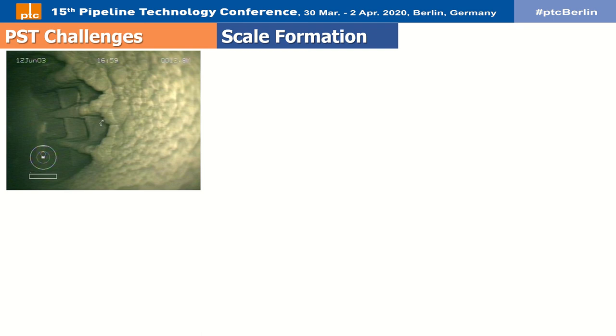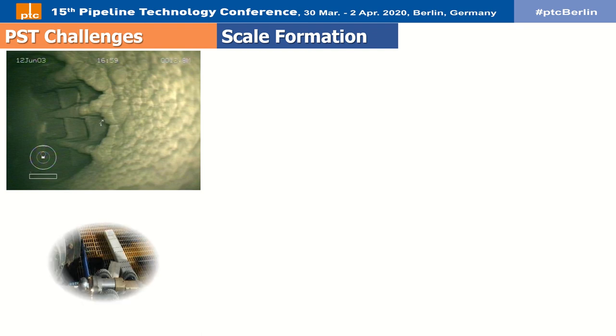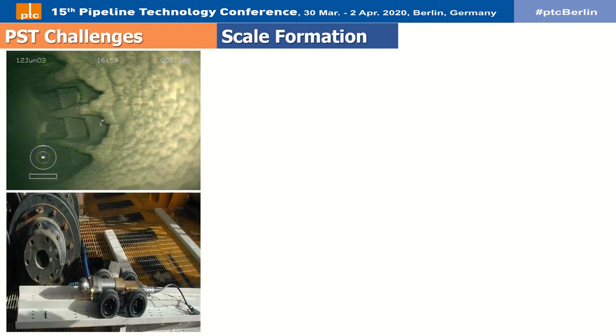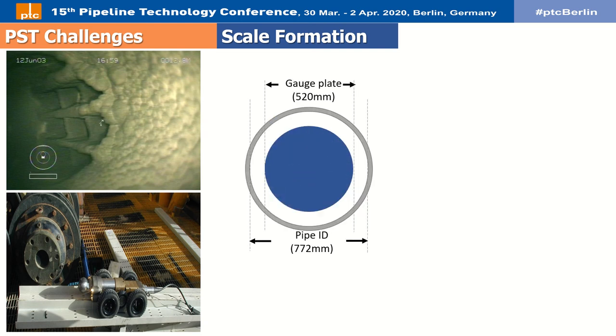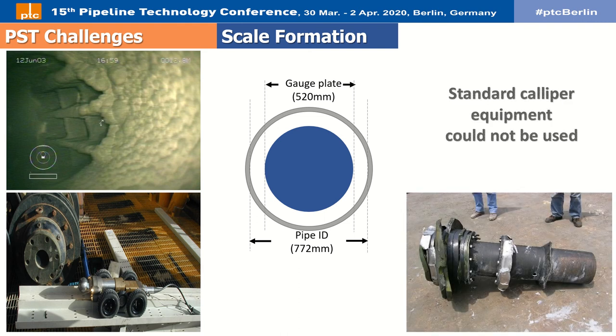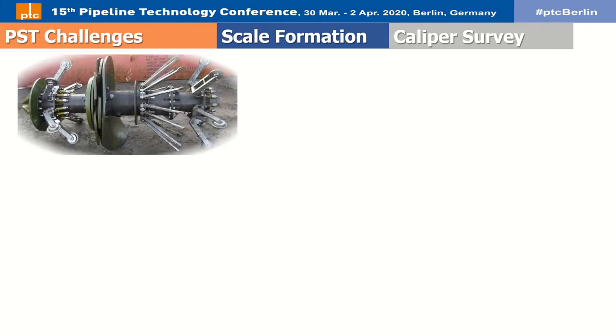Following pressure drop and flow assurance issues noticed on sea lines in 2003, just a few years after operation, it was decided to run a caliper pig to identify and quantify the amount and distribution of scale inside the pipelines. At the first step, a gauge pig was run to obtain preliminary data on pipeline clearance. Severe damage to the received gauge pig clearly indicated that scale deposit thickness was much greater than anticipated, also demonstrated by CCTV inspection. Consequently, a special caliper pig tool was required to pass inside the pipeline given the scale significance.